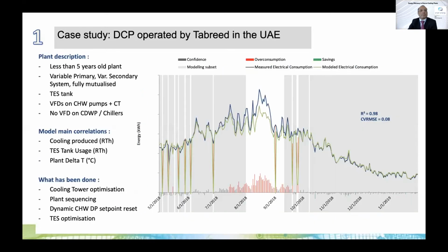So the second case study is a Tabreed plant, which I believe is fairly representative of the average district cooling plant in the region. It's fairly new, less than 5 years old. It's about 30,000 RT, and it's got a primary variable secondary system, fully mutualized with TES tank and VFDs on the chilled water pumps and the cooling towers, but not on the condenser pumps and on the chiller compressors.